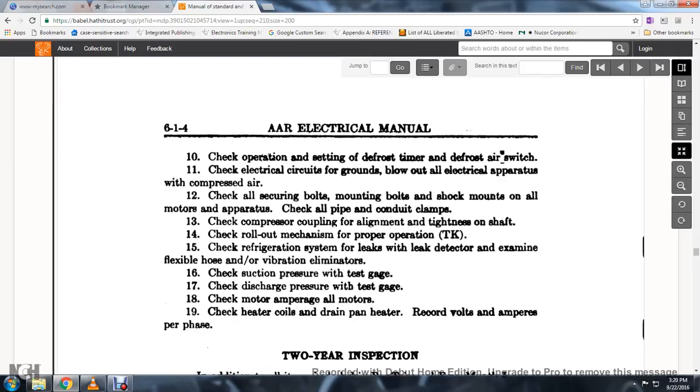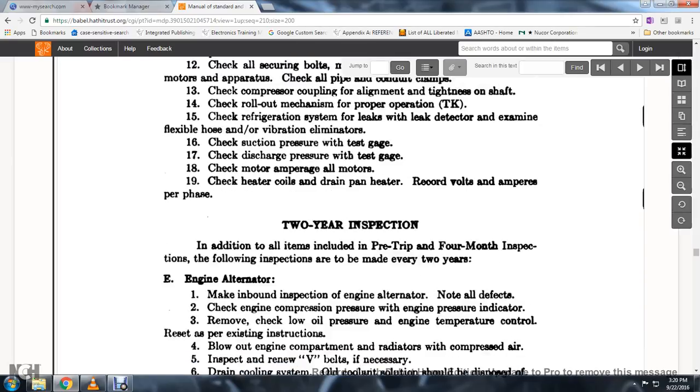Check operation and setting of defrost timer, and defrost air switch. Check the electrical circuit grounds and blow out all electrical apparatus with compressed air. Check all securing mounting bolts and shock mounts on all motors and apparatus. Check all pipe and conduit clamps. Check the compressor coupling alignment and tightness of the shaft. Check the roll-out mechanism for proper operation. Check the refrigeration system for leaks using a leak detector. Examine the flexible hose vibration eliminators. Check the suction pressure with a test gauge. Check the discharge pressure with a test gauge. Check motor amperage on all motors. Check the heater coils and drain pan heater; record volts and amperes.